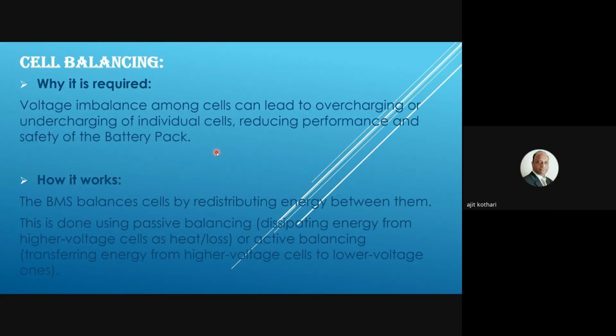So the second cell will get charged only at the floating current rate, which takes much more time. If the expected charging time was 2 or 3 hours, it could now take more than 12 hours, since it's charging at the floating current only, which is much less than normal charging current, typically around 10% of it. So your charging time can increase by about 10 times.